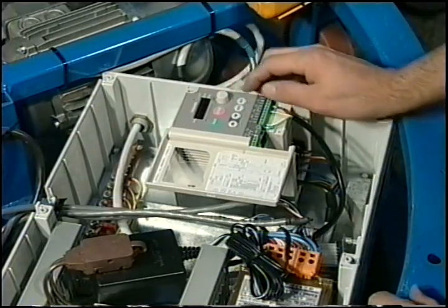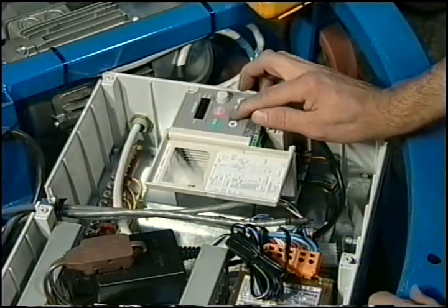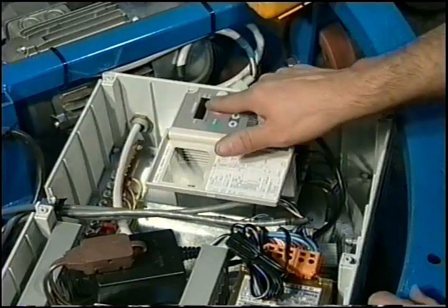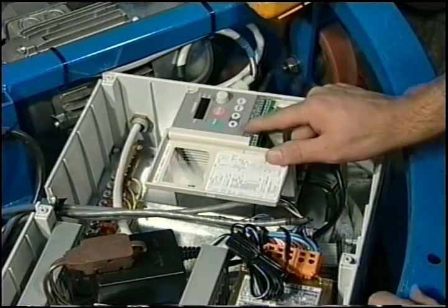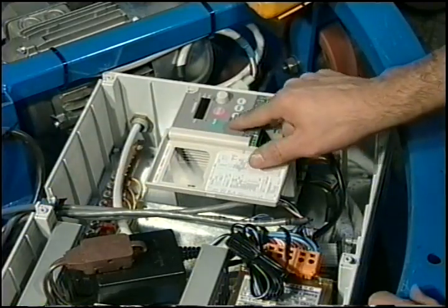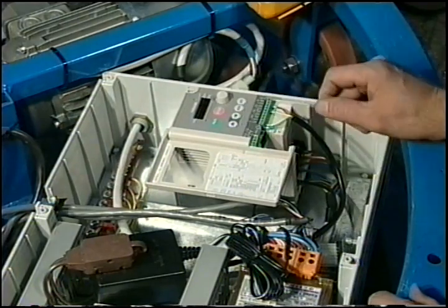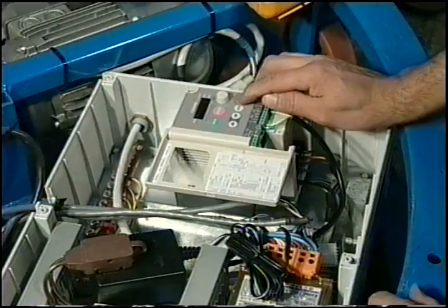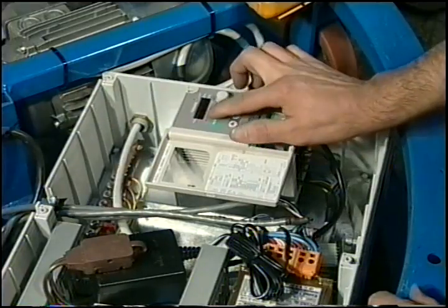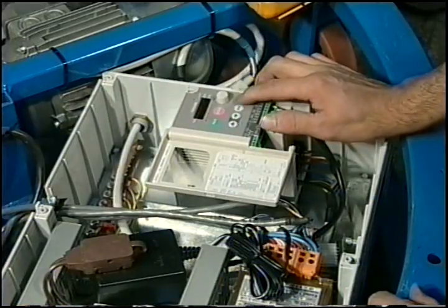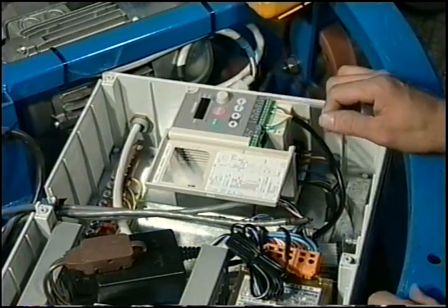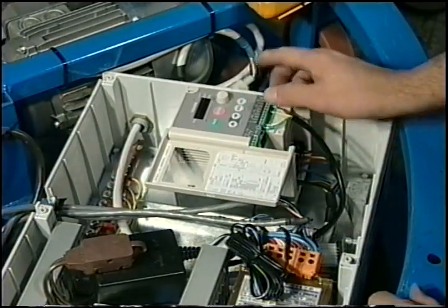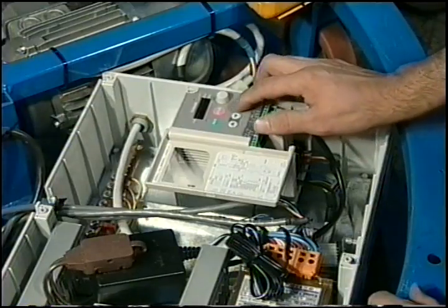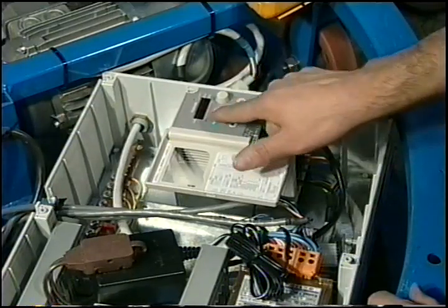If you set it to a value of 1, using the arrow keys, like just now I hit the down button, I changed it to 0, which is where yours is going to be. If you hit the up button, it's going to change that value to 1. Then you're going to hit the enter button to save that value. You're going to see your display flash twice. Then if you hit enter again, you're going to see that changed value. Once you're all done, you can hit the MON button 3 times, and it's going to go back to your original setting of 0.0.